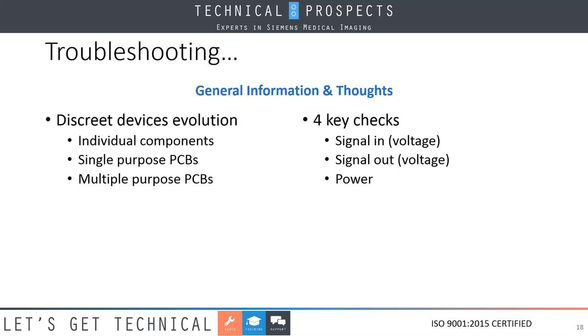The third thing here is power. Are all our power supplies proper? Very, very important. Especially on multiple purpose PC boards, you may have 8 or 7 or 5 different power supplies on that board. You've got to verify them all. The reason I say this is too many times I have seen where one circuit on a board will only use one of the power supplies. And I've watched people change out a board when in fact the reason that function wasn't working is because the power supply had a problem. But because all the other circuits were working, they never checked all of the power supplies. It is incumbent and imperative upon you that you do all these four checks.